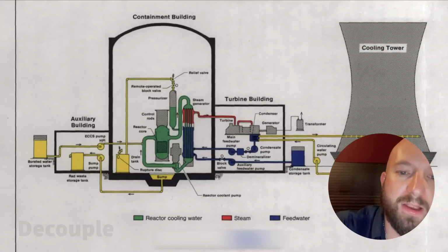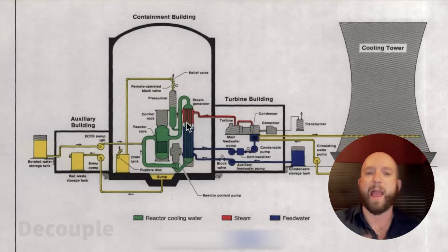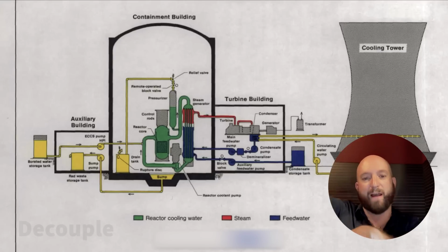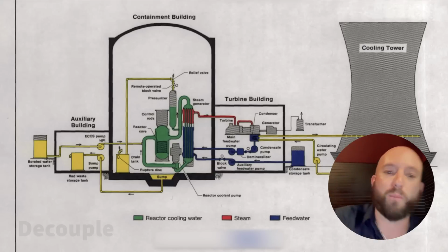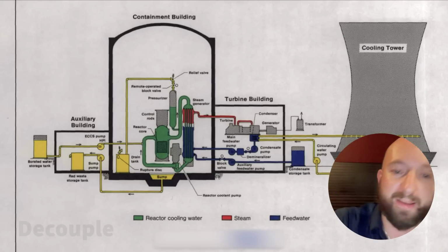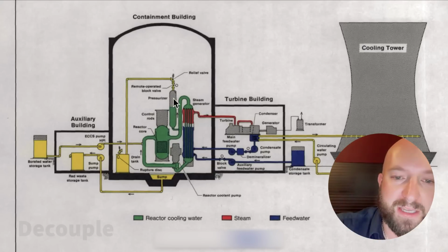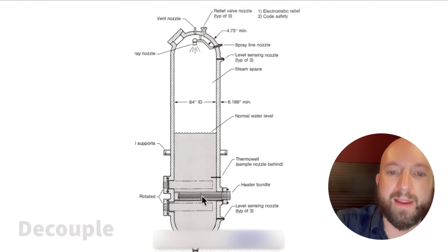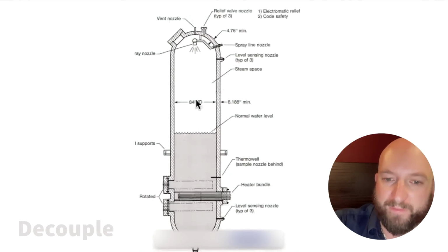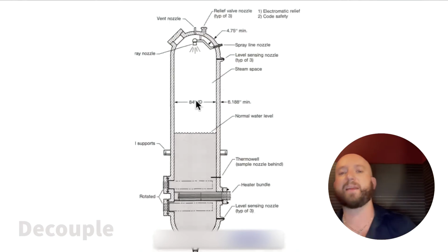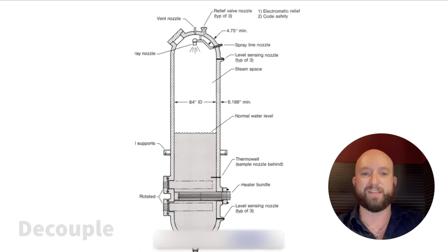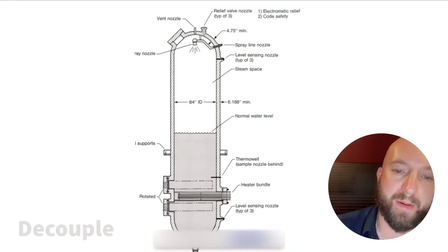It's a device called a pressurizer. Remember how I said this system is ideally at 2,195 pounds per square inch. The pressurizer is a big tank. At the bottom of the tank, and this is what it looks like at 3 Mile Island, it has heaters. And there's a big steam bubble at the top. That's the only place, ideally, in that system where we have steam on the primary system.